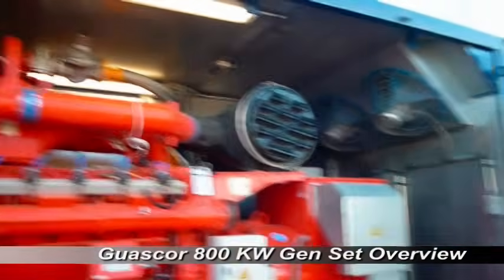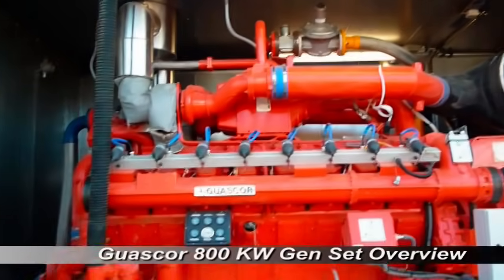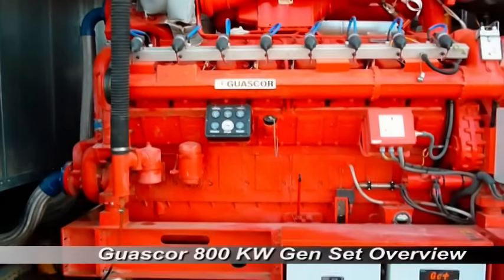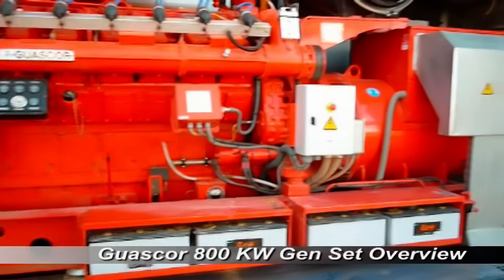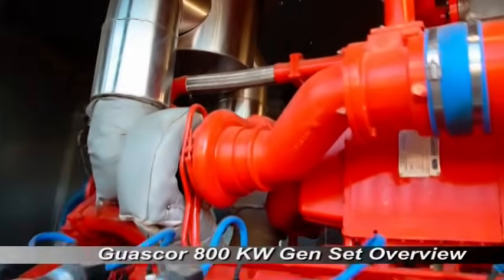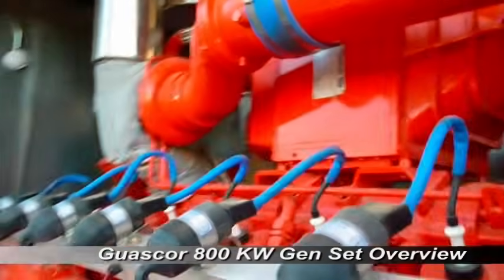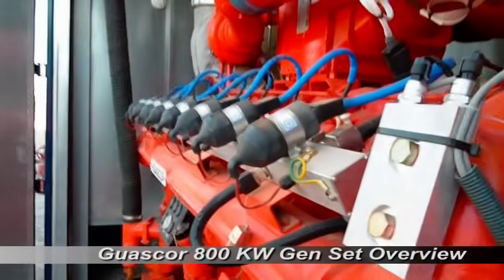The generator sets used in the project were produced by Guascor. They are fueled by low methane gas (45% methane), have a maximum power capacity of 800 kilowatts, and are water cooled by two external circuits suitable for desert ambient temperatures up to 55°C. The sets are capable of operating 24 hours per day, producing no emissions. The engines are turbocharged and after-cooled, working at a speed of 1,500 revolutions per minute at 50 Hz, with a 16-cylinder V configuration.